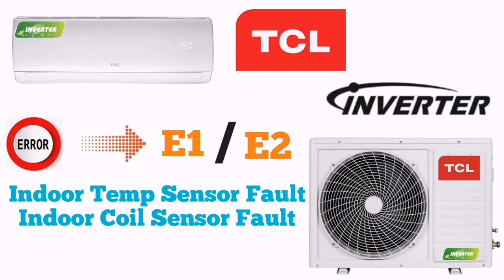When you see error E1 or E2 on your indoor display, E1 means indoor temperature sensor faulty and E2 means indoor coil sensor faulty. First of all, you have to check the placement of both sensors. If the placement of both sensors is good, you follow the next step. If the placement is not good, place them in the proper place and try to start the unit.